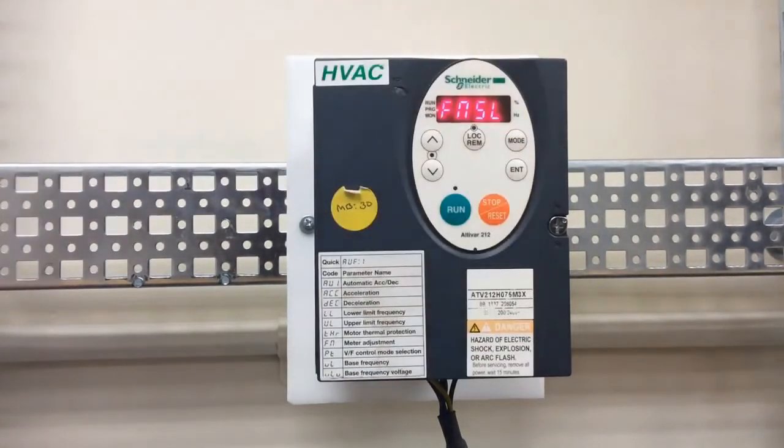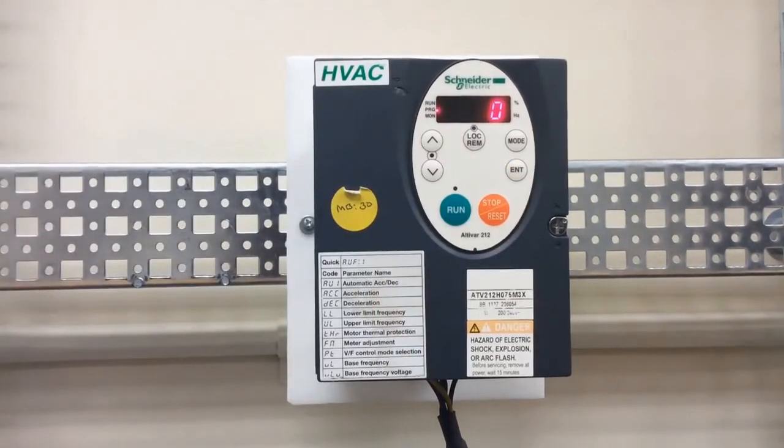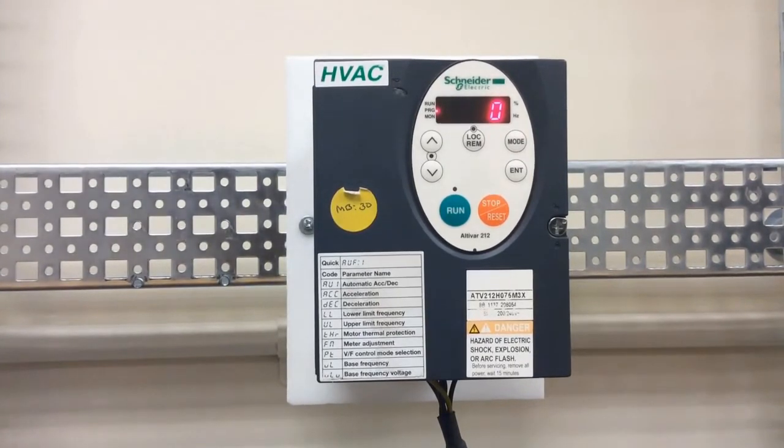The next parameter is CMOD, which tells the drive where your start and stop commands are coming from. The factory default is zero, and zero is for terminal control, which is what we want for two-wire control.